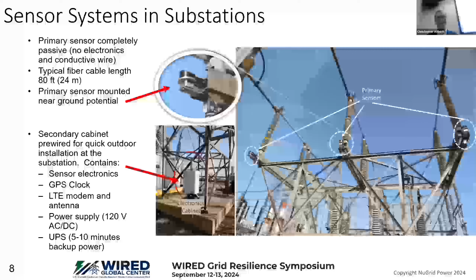Some waveforms, you'll see in these slides. In the interest of time I won't go through it all, but the concept of traveling waves is not new. The fault happens, two step responses go in two different directions toward two substations. You measure the time difference and you know where it is. The point though is, if you measure it at a typical relay sampling at 10 kilohertz, at the very bottom of that you'd know the location only within 30 kilometers or 20 miles.